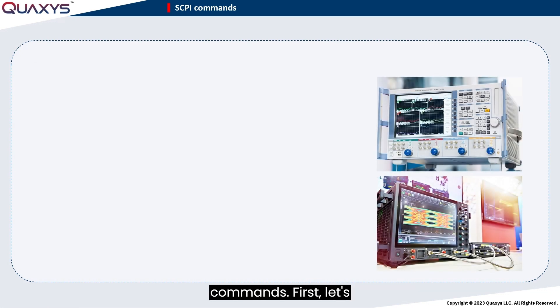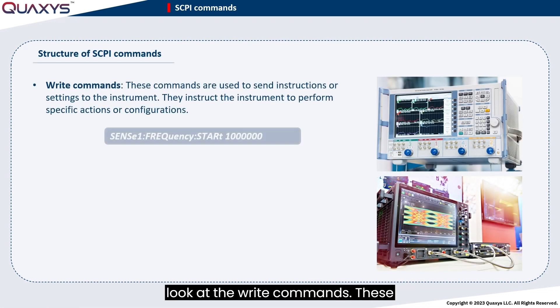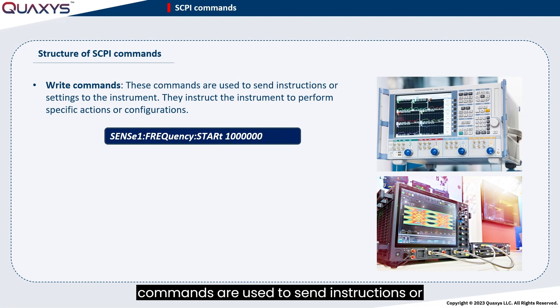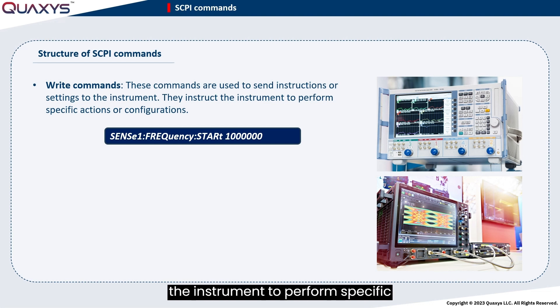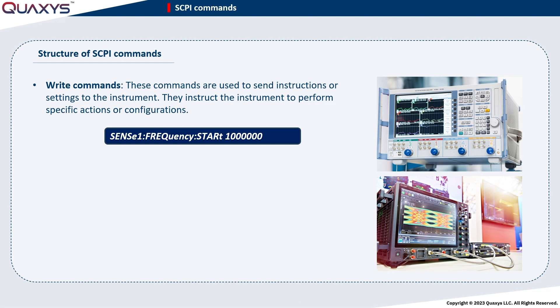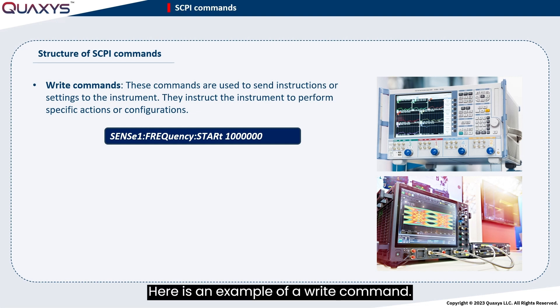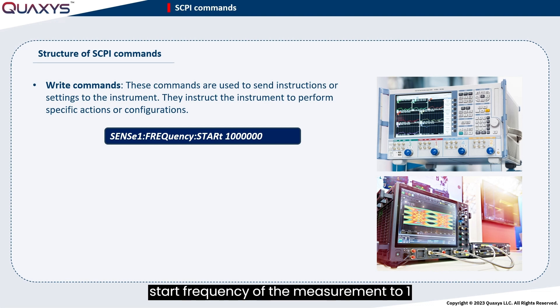There are two general types of SCPI commands: write commands and query commands. Write commands are used to send instructions or settings to the instrument. They instruct the instrument to perform specific actions or configurations. Here is an example of a write command — this command instructs the VNA to set the start frequency of the measurement to 1 MHz.